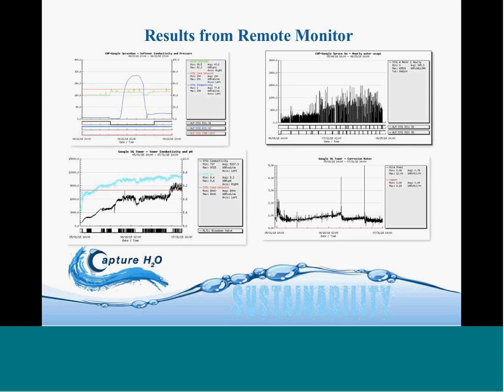Again, this slide shows results from the program. You can see the pre-treatment system monitor graph up on the left-hand side. It shows water pressure, and when the system regenerates, it shows a curve. Our water consumption is on the right. On the lower left, the tower conductivity rises as we eliminated the blowdown. And the bottom right shows the corrosion rates for the steel and copper. Our steel is less than 1 mil per year, and our copper is almost 0 at this point.